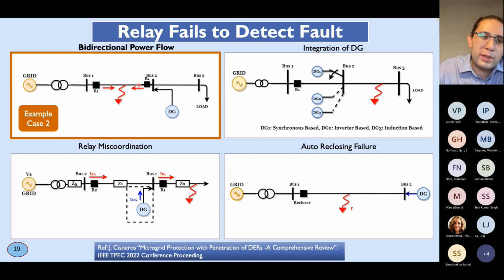And same as before, I will explain case 2 here, which is the bidirectional power flow. As we could see in the traditional protection, we have a line where we have a fuse, we have reclosers, and we also have the relay, which operate, but they won't operate in case we have a DG installed, because we will be feeding from both sides. The traditional way only considers feeding on one side, let's say the left-hand side or the distribution level, or it's coming from generation, and we just consume in the load.